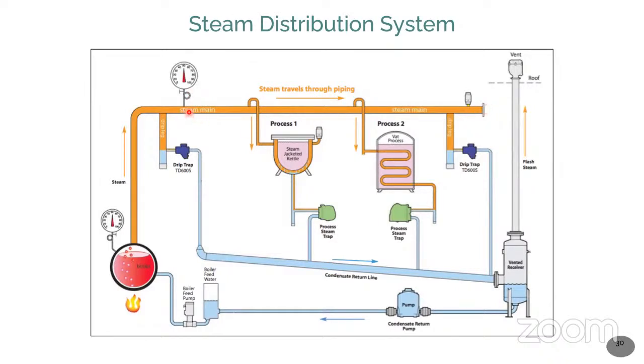Number one, the system itself has some resistance, so because of that, the drop will occur. Number two, you are using the steam for your process. When you are using it for the process, automatically a pressure drop will be there. So if you measure the pressure here and the pressure here, then definitely there must be a drop, something similar to a voltage drop in the equipment, in the line.